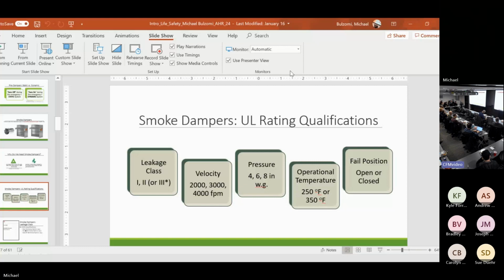I'm at an air handler. I have a lot of air coming through, I have high velocity ductwork. There should be a reason why you're stressing it. Operational temperature. Smoke dampers are not fire rated. They have nothing to do with fire. They control the movement of smoke. This temperature is the rating on the actuator, 250 degrees or 350 degree maximum rating. 350 should only be used for engineered smoke control systems.